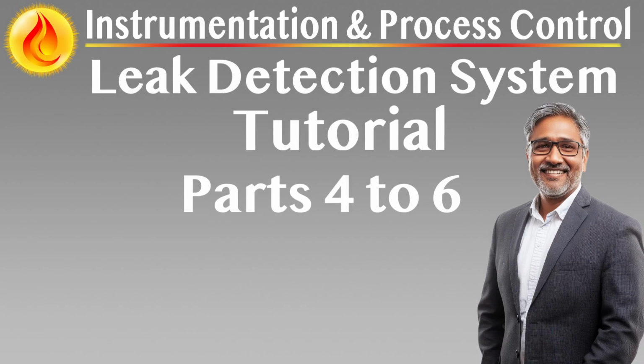Instrumentation plays a pivotal role in system performance. The accuracy, stability, and placement of pressure, flow, and temperature sensors directly affect the LDS's ability to detect leaks and reject false alarms. Instrumentation specifications should be reviewed with the LDS supplier to ensure compatibility with the detection algorithms. Where high performance is required, analog to digital conversions should offer at least 12-bit resolution, and care must be taken to minimize signal noise and latency. Thermal effects from solar exposure should also be mitigated through insulation or subsurface sensor placement.